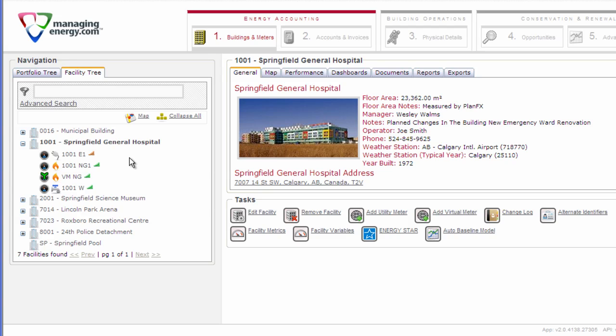small number of meters. Managing Energy defines two categories of utility meters. The first category is physical meters, which are physical pieces of hardware which produce regular readings. The readings may be collected manually or electronically. This is what we normally think of as a meter.